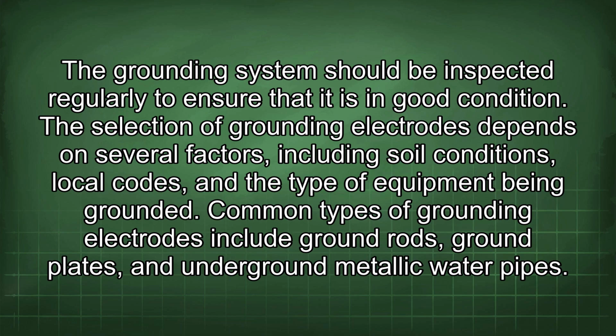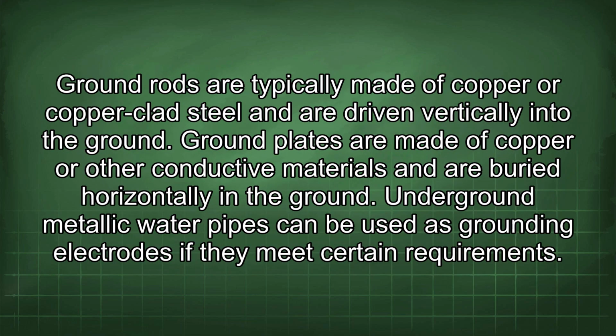The selection of grounding electrodes depends on several factors, including soil conditions, local codes, and the type of equipment being grounded. Common types of grounding electrodes include ground rods, ground plates, and underground metallic water pipes. Ground rods are typically made of copper or copper-clad steel and are driven vertically into the ground. Ground plates are made of copper or other conductive materials and are buried horizontally in the ground. Underground metallic water pipes can be used as grounding electrodes if they meet certain requirements.